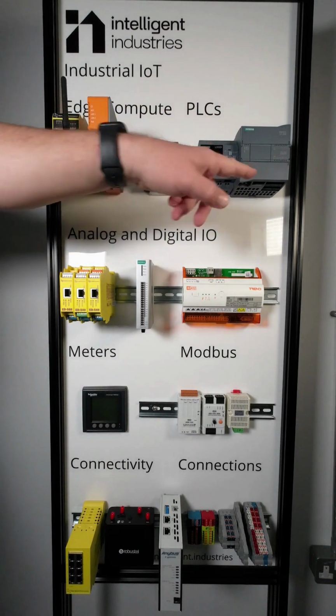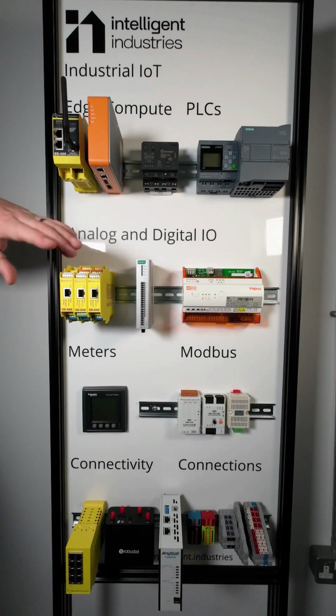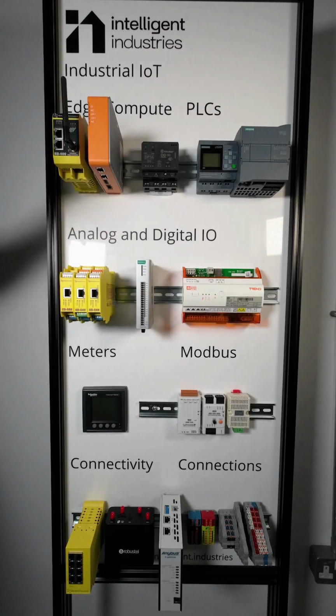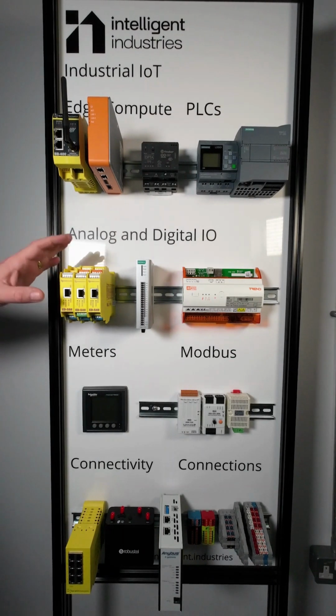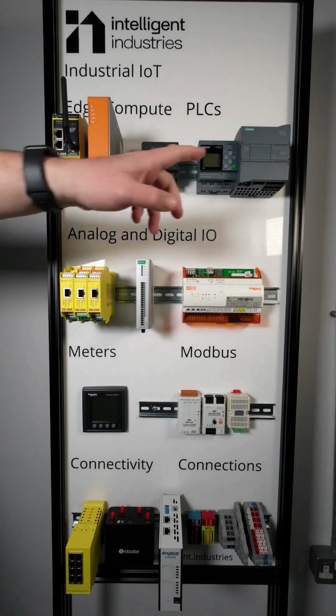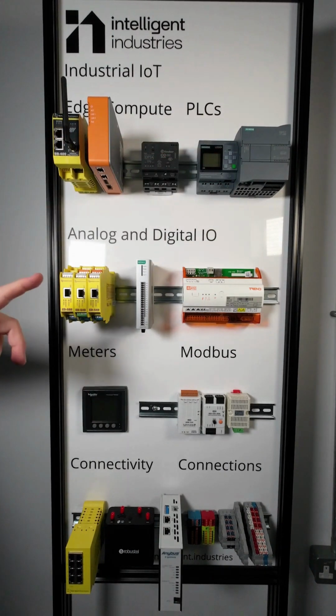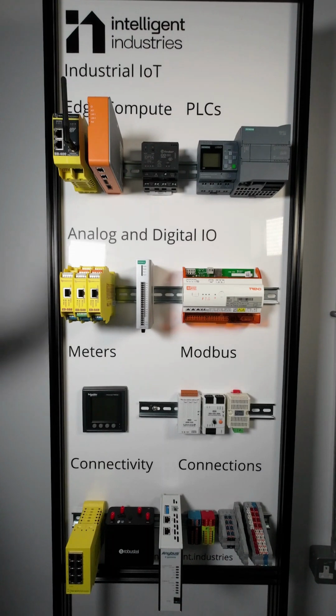This PLC could be reading from these input modules, waiting for the signal to change, detects the signal change, and then the launch sequence starts. When it comes to our analog I/O, perhaps the launch sequence that's been initiated by this PLC tells one of our analog output modules to send an analog signal to a drive controller, and that drive controller will determine how fast the motor spins, and so how fast the winch operation happens.